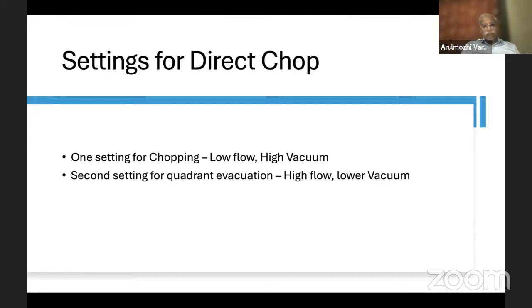Why do you want to keep the flow low during direct chop? You don't really want to aspirate anything. You really want to get hold of it. But when you keep low flow and high vacuum, the time taken for the vacuum to build up becomes too long. So with the newer machines, you can have a low flow, high vacuum, but you can set the rise time to be very low. You can keep the rise time to be 1 second or half a second, so that though it is a low flow, high vacuum, the vacuum, once occlusion occurs, is built up very rapidly. So you can still make the surgery very fast by keeping the flow rate a little low for your own safety.